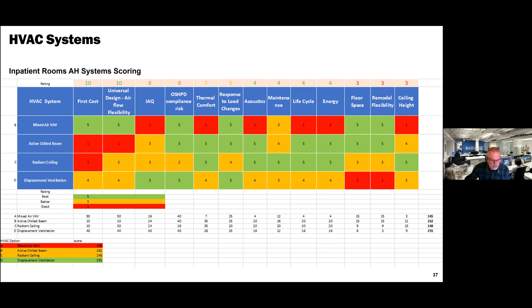And to some extent, what it came down to was weighing the points rather than counting the points. And what I mean by that is one of the criteria, which has to do with the standardized ICU room, pretty much said that that second column, universal design and airflow flexibility, became the ace. We had to have the greatest flexibility there in the right system to really achieve that. And to some extent, despite the points that accumulate across the other issues, that became the deciding factor with the HVAC system.